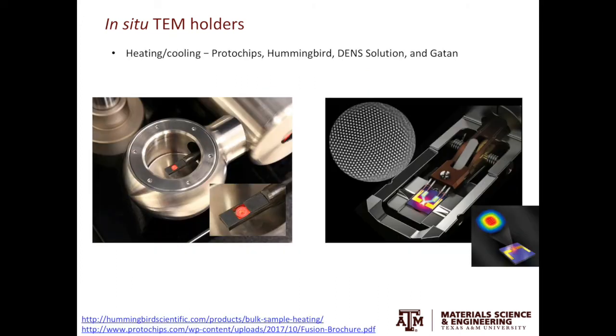In addition to mechanical loads, you can also apply heat to your specimen. There are two types of heating holders. The one on the left heats up the entire specimen. So the TEM holder itself is like a miniature furnace. The second type of the holder utilizes the MEMS device, and the heating is much more localized. In this case, it's a very small area in this chip that is heated. Companies that sell heating or cooling holders are Protochips, Hummingbird, DENS Solution, and Gatan.